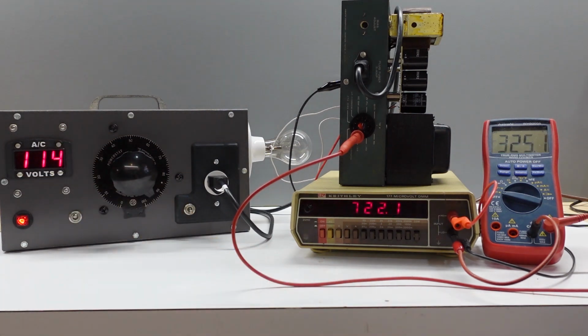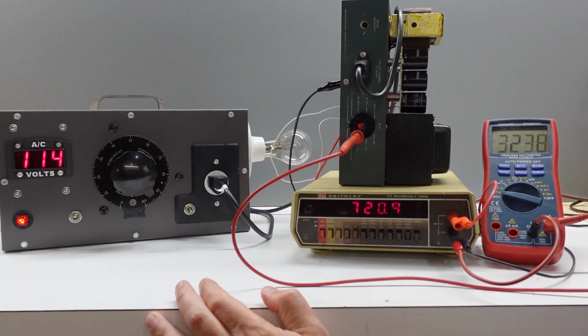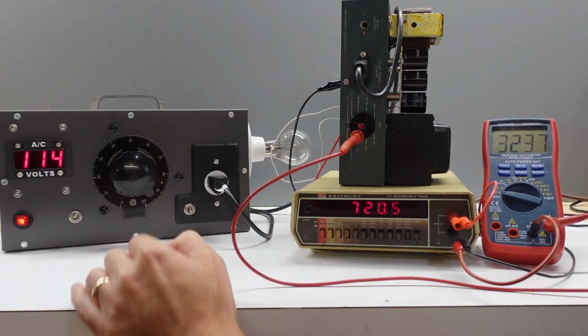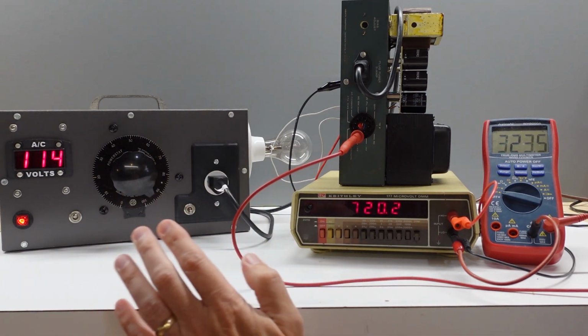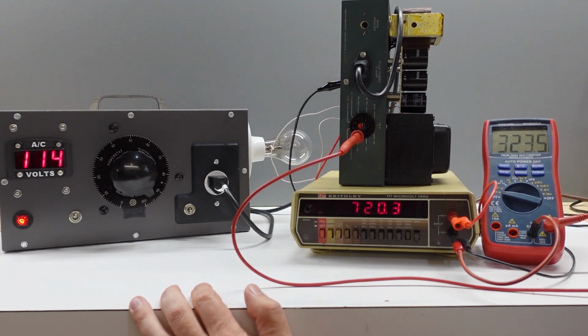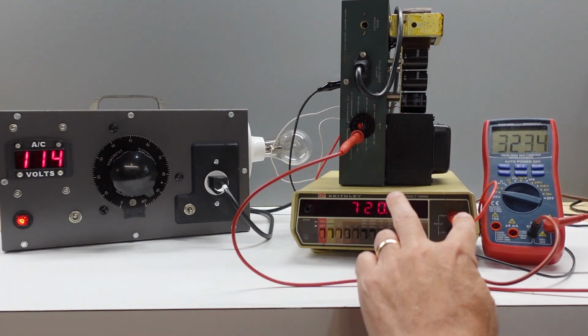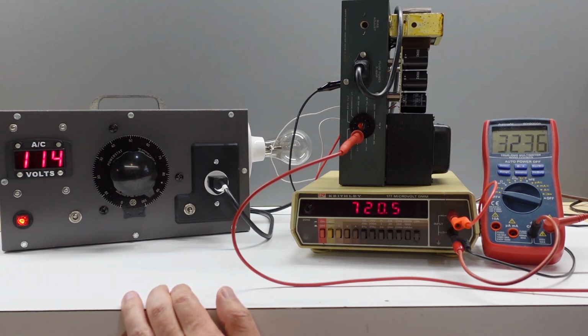I'll stop it there around 115 and see where we are. Got about 720 volts on the high voltage, 323-ish on the medium voltage. That looks good. It may not come up on the camera, but there's a very slight glow in the bulb, and that's fine, just a little bit of power being drawn by the transformer without a load on either of those two circuits. So that looks pretty good.